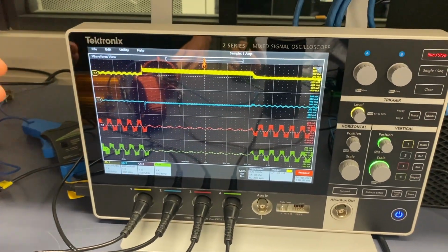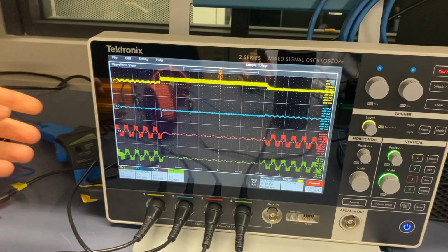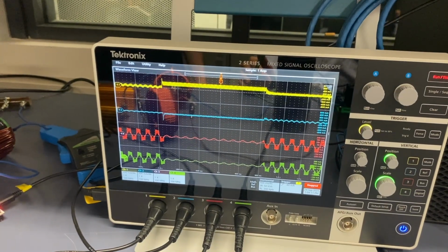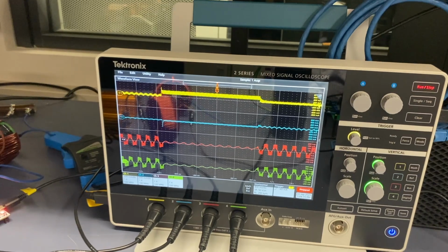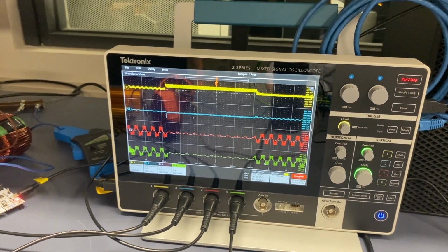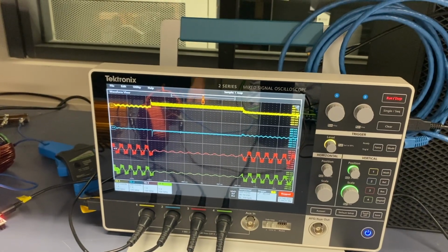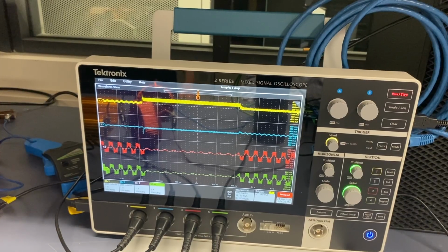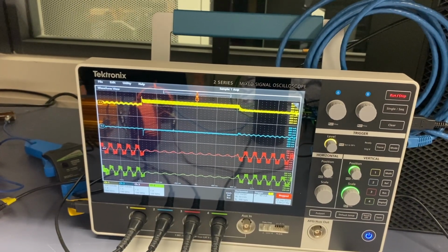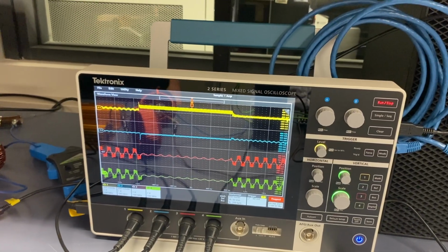So first we have the zone 1 current, which is positive, and then you'll notice that the zone 2 current is negative because the DC link capacitor from zone 2 is going back into zone 1 because that is where the short circuit is. And then you'll notice that the AC current for both terminal 2 and terminal 3 loads is reduced because all the power is now going into the fault short circuit.